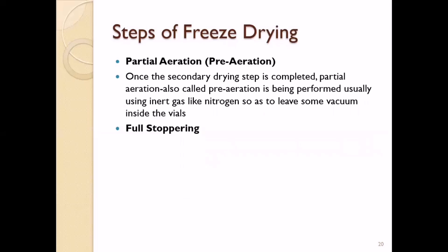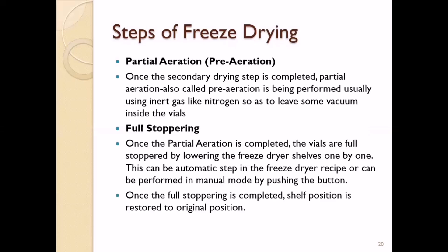After partial aeration, full stoppering is performed to fully stopper the vials so there is no contact with the external atmosphere, and the freeze-dried product inside the vial maintains its moisture content and required physical and chemical characteristics during shelf life. Full stoppering is achieved by lowering the freeze-dryer shelves one by one — this can be an automatic step in the freeze-dryer recipe or performed in manual mode. Once full stoppering is completed, the shelf position is restored to its original position.